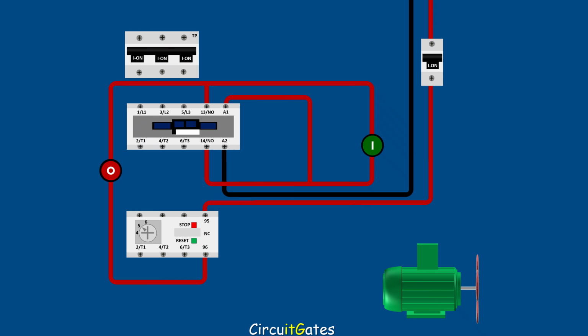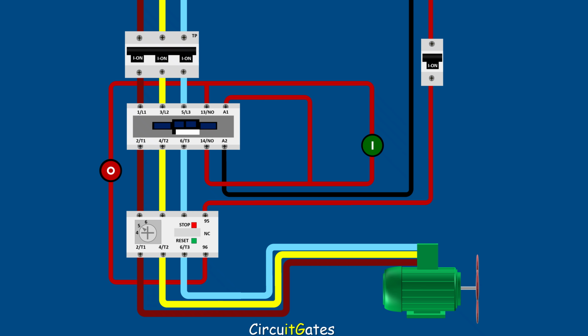When connecting the power circuit to the electric motor, we take the 3-phase conductors from the supply and connect them to the triple pole circuit breaker. From the triple pole circuit breaker, the 3-phase conductors are connected to the contactor. From the contactor, the 3-phase conductors are connected to the overload relay. And after the overload relay, the 3-phase conductors are connected to the electric motor. The joining and separation of wires are made at the components' contacts, not on the wires themselves. In this video, we are joining the wires for clarity, so you can see much better.